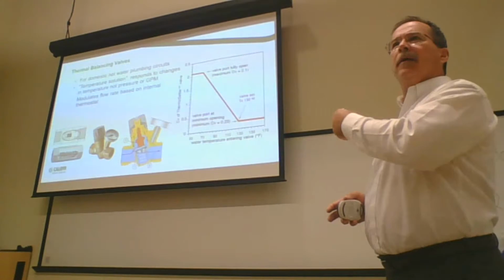So these are the only valves that actually modulate open and close, like a modulating control valve. And what that does is when they're open, that circuit has most of the water, okay? When they start to modulate down closed, it pinches off the water coming to that circuit. What's that do? It pushes the water to the next circuit, right? Let me go ahead and advance the slide.